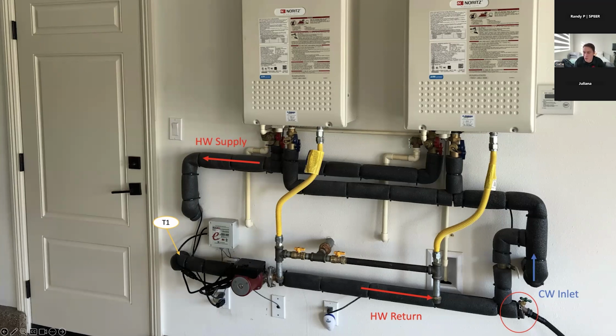And then downstream of this bleeder valve, you want to make sure that you have either an isolation valve or a check valve or something that prevents backflow, because if you open up this hose bib and you don't have any type of check valve or isolation valve here, then what's going to happen is the cold water from the city is just going to come in and short circuit, and you're never actually going to bleed out the return line. So that's why things have to be done in the right order.